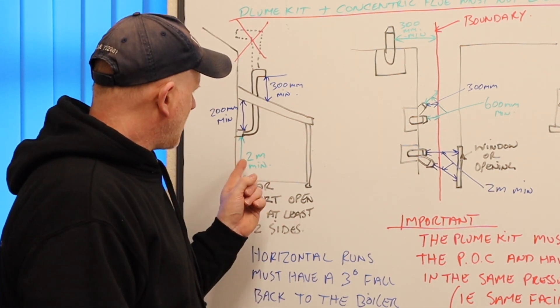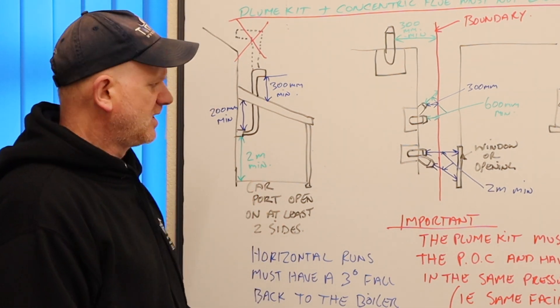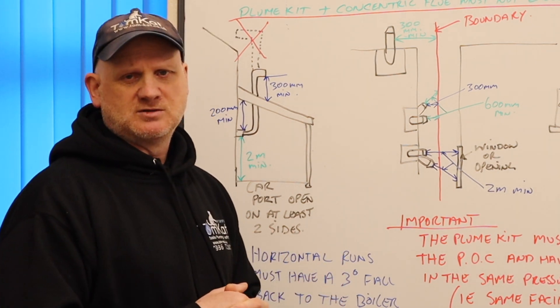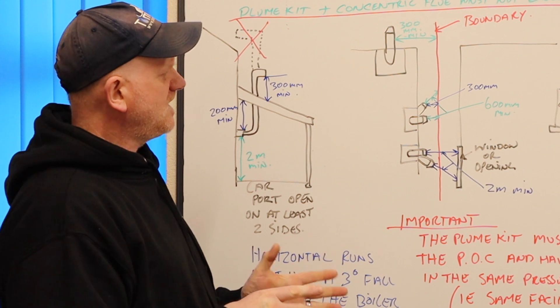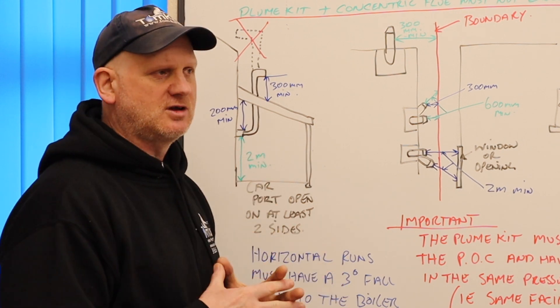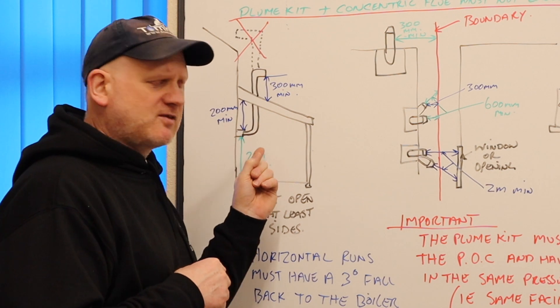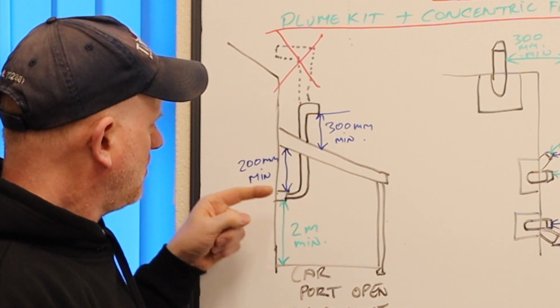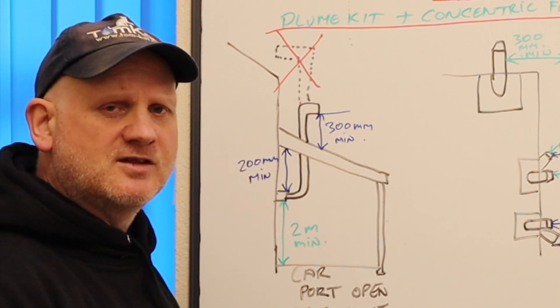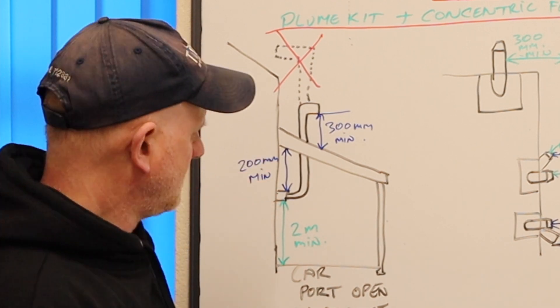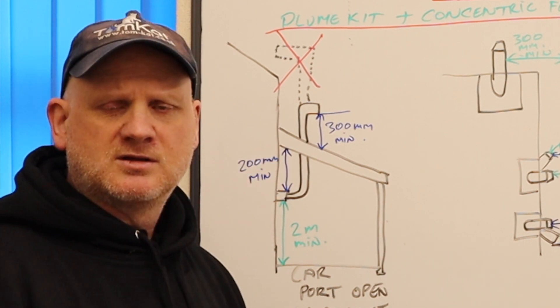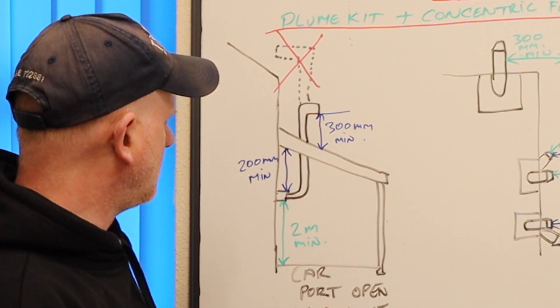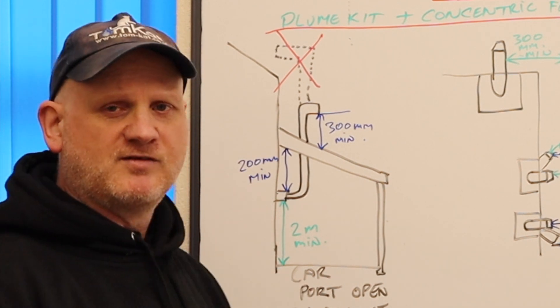First one is this carport one we've got here. Now again, if the manufacturer says you cannot do this, then you can't. But I know Baxi and Worcester, if you've got their flue system under a carport, prefer you to do this. So we need to still install the flue as it should be. So 200 away from the eaves or the carport, but we still need to be 2 metres off the floor.